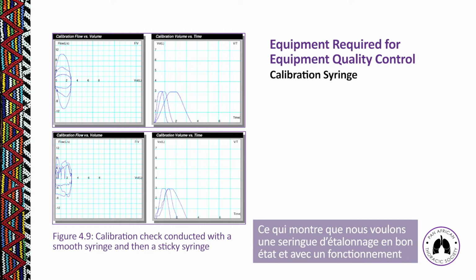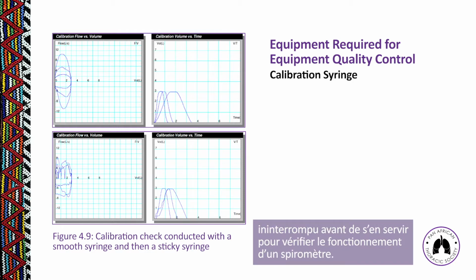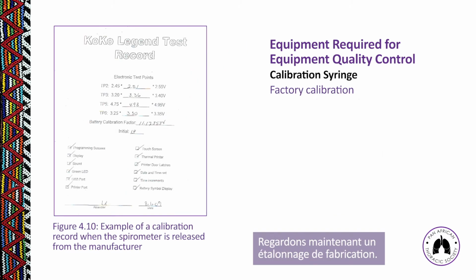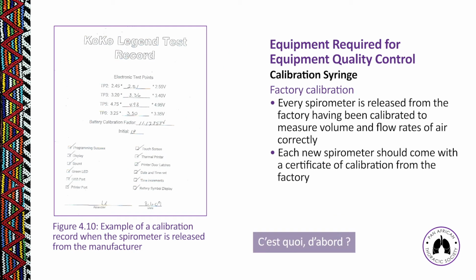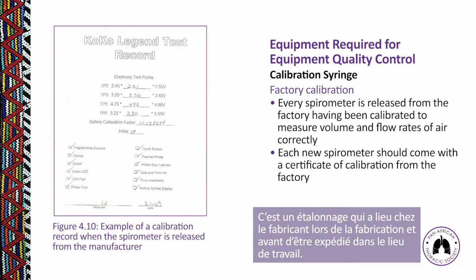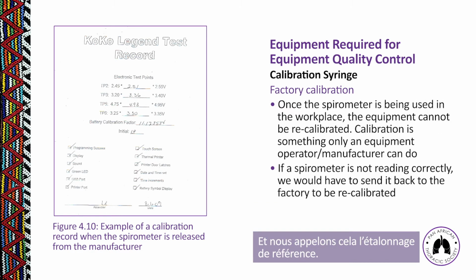So we want to make sure that our calibration syringe is well cared for and that it's in good working order before we use it on a spirometer to make sure that it is working correctly. Let's look at a factory calibration. What is factory calibration? That is the calibration that is conducted on the machine in the factory before that machine gets sent out into the workplace. And we would term that the baseline calibration.